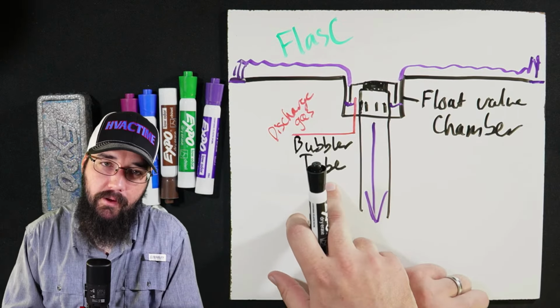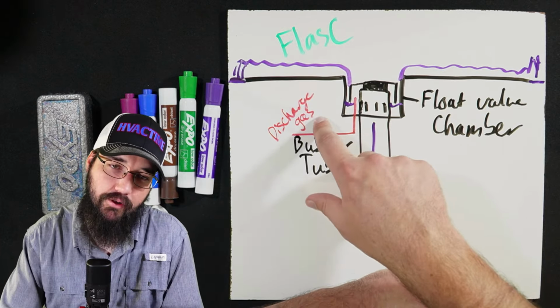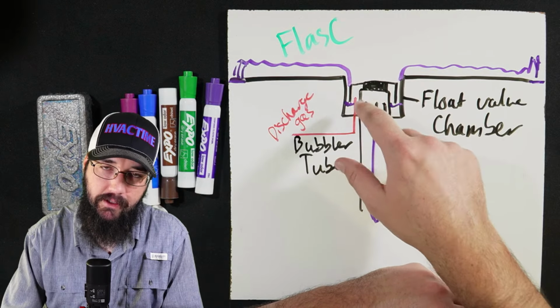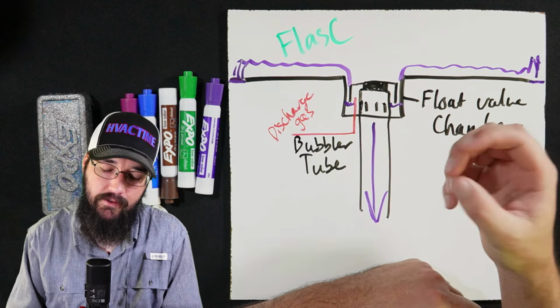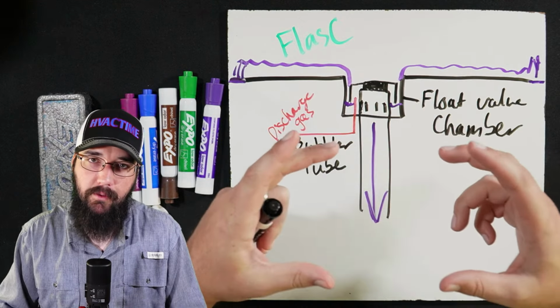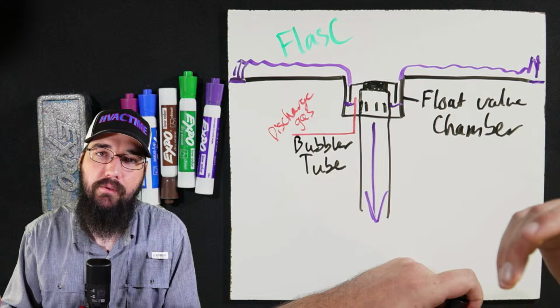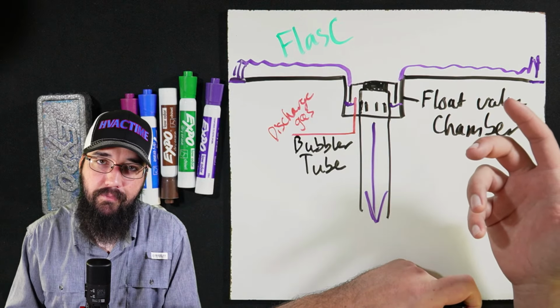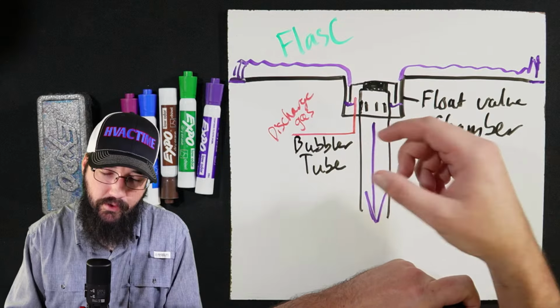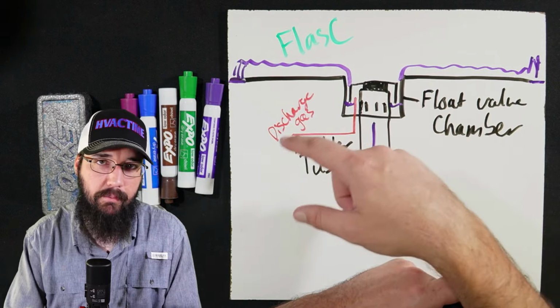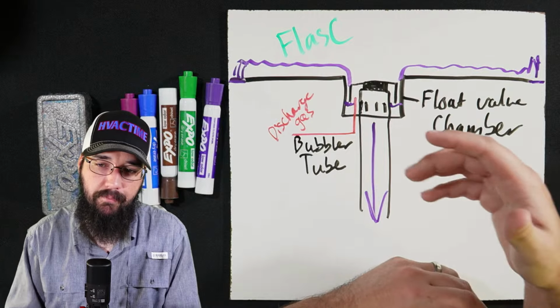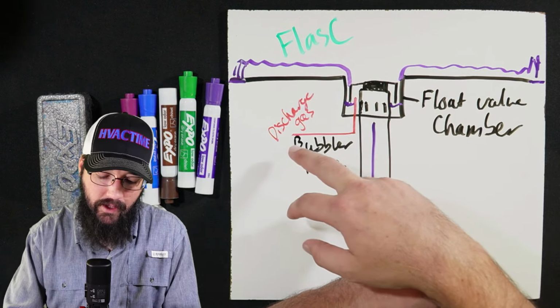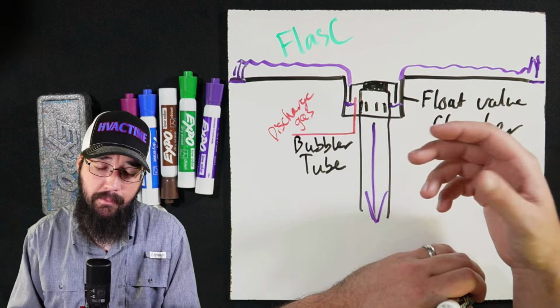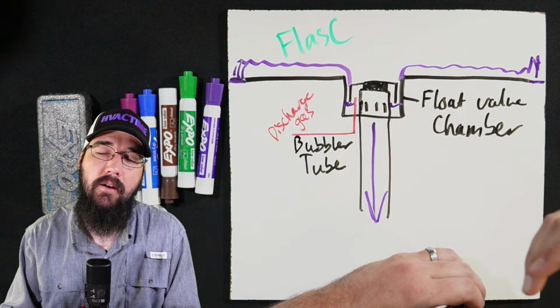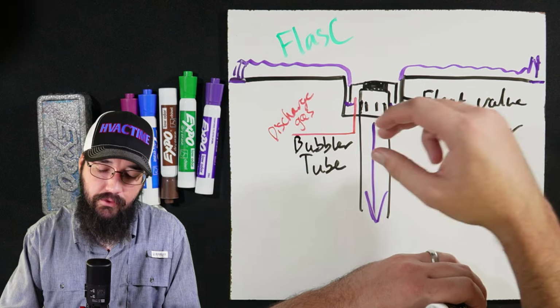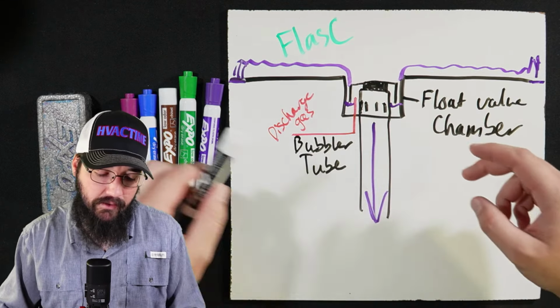This bubbler tube's job is to take some discharge gas and fill the underside of this upside down bowl with vapor. That is its core function. It's a very small tube. It's not trying to be a hot gas bypass, which is one of the concerns we have with a design like this. It's not letting this tube become a hot gas bypass, but it is allowing just enough vapor into this bowl that the vapor gets trapped.